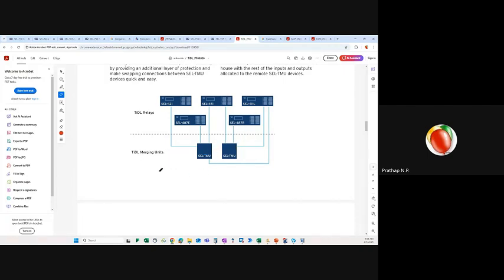Let's say you have a line, transformer, bus bar, breakers, and CTs. Take just the differential protection of a transformer, and you'll have this connected. This TMU, TIDL merging unit, stays as close as possible to the transformer, just underneath it in the control panel. So from that place all the way to the control house, you only have fiber.